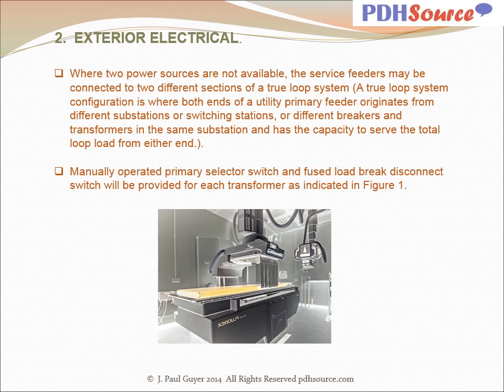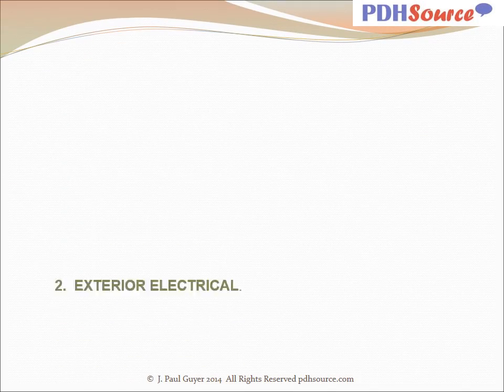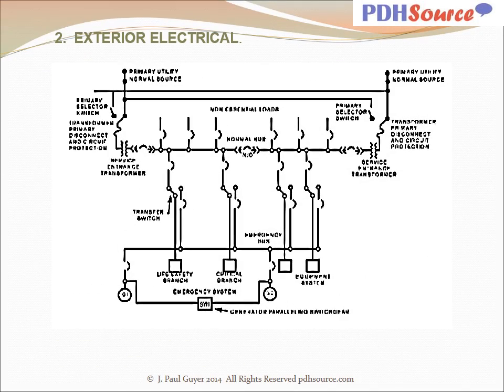loop system. A true loop system configuration is where both ends of a utility primary feeder originate from different substations or switching stations, or different breakers and transformers in the same substation, and has the capacity to serve the total loop load from either end. Manually operated primary selector switch and fused load break disconnect switch will be provided for each transformer as indicated in Figure 1. Figure 1 is indicated here on slide 16.